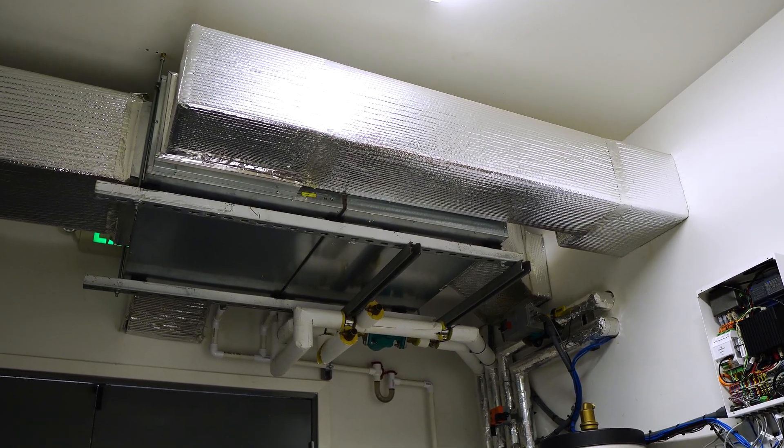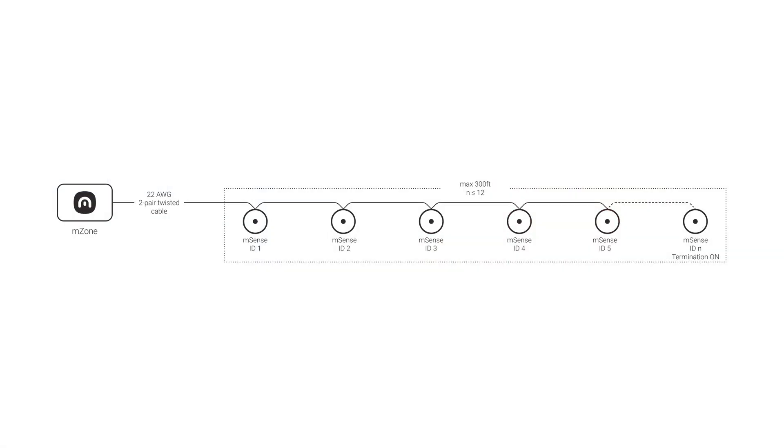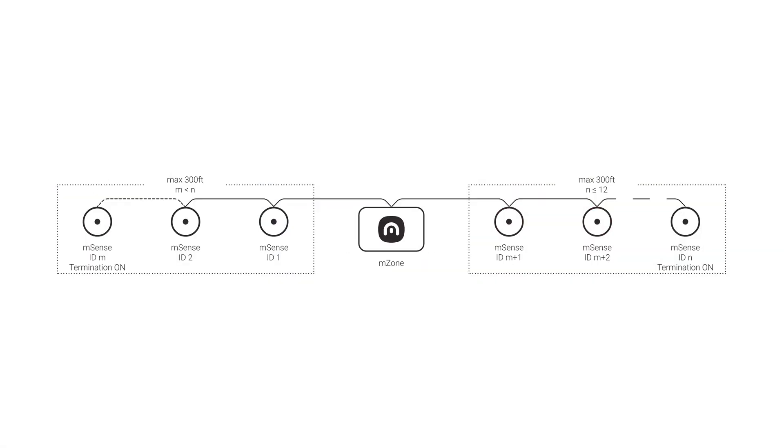All of these sensors will be hardwired to our controllers. You can daisy chain them together or create separate branches, but they will all be connected to our controllers. They'll be mounted at about five to seven feet—head height—and we want to make sure they're mounted out of direct sunlight.